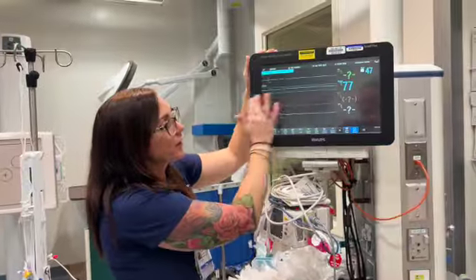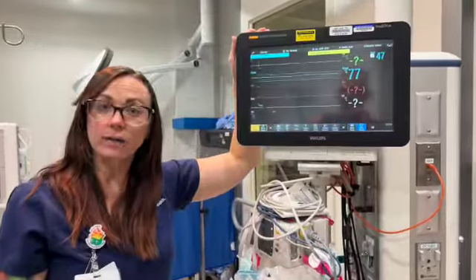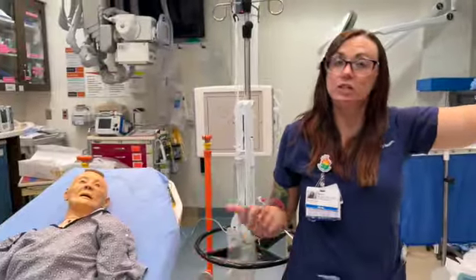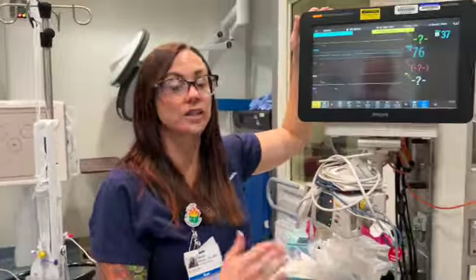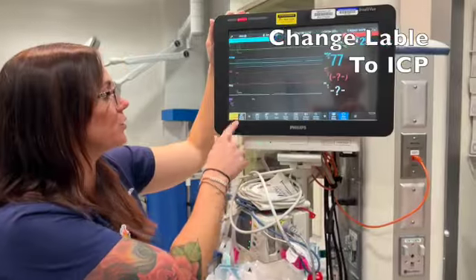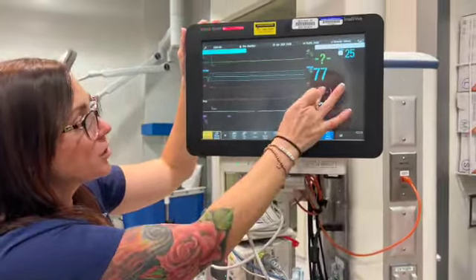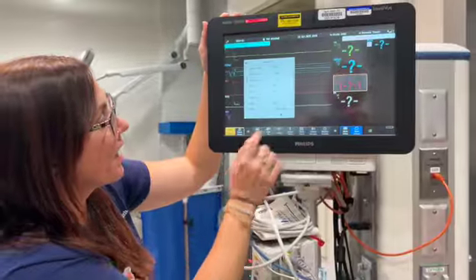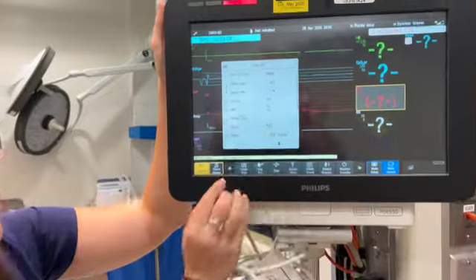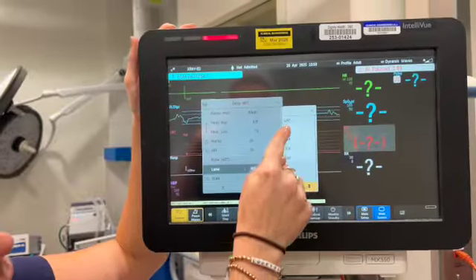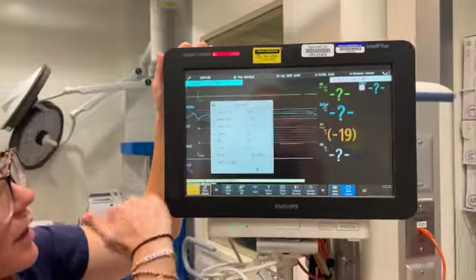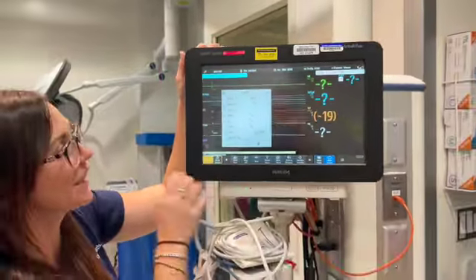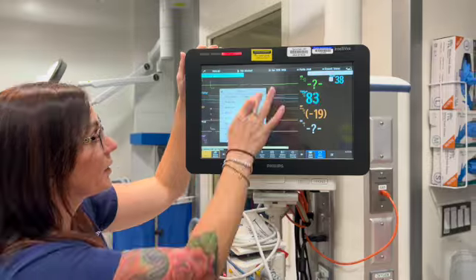This particular pressure section is saying art line. What we're going to be doing here is measuring ICP. So in order to do that, we need to change the label. I'll show you how to do that. First, you're going to touch right here, and then where it says label, press again, and change to ICP. Now you'll notice a different color will come up on your screen to indicate that it's measuring ICP.